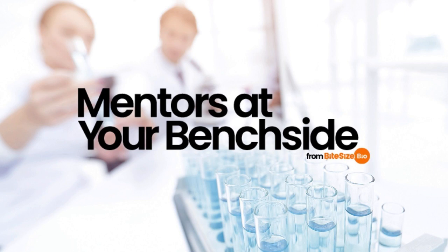So after you've cleaned everything, you might need to check the accuracy of your scale as well. So why is it important to do this, and how do you check accuracy? First, you want to ensure that your scales are completely free of residue before you check the accuracy. Now, accuracy is how reliably the scales are at measuring the weight of a sample, and this can be deduced by several tests that are designed to help you ensure that your scales are functioning at peak efficiency.